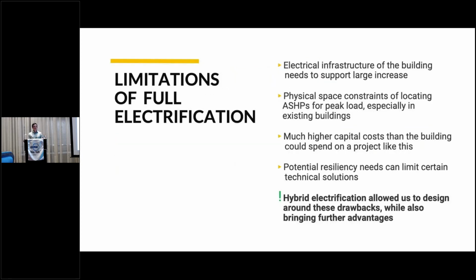Going back to that full electrification project, as we were designing it, we started running into design challenges that put a damper on fully electrifying the building. First and foremost, full electrification requires a large additional electrical capacity that most buildings can't handle without a feeder upgrade, so a Con Ed project would have had to be explored, bringing in a whole new electric service.